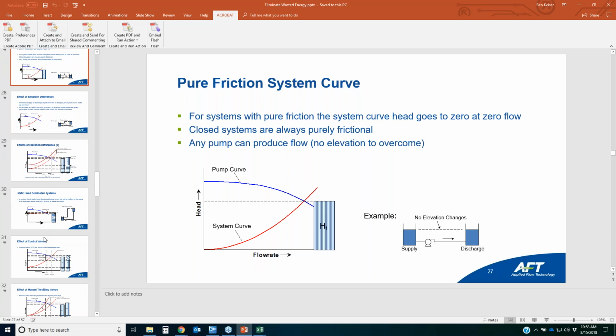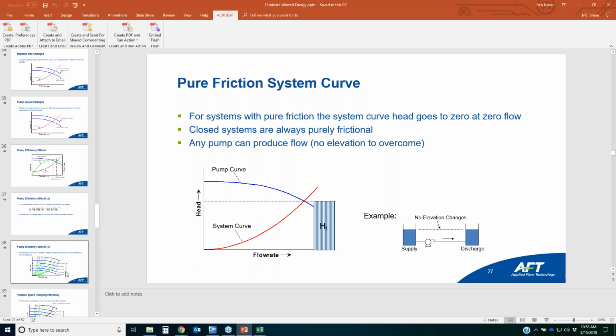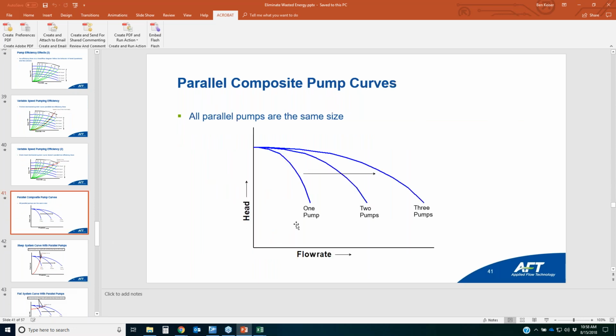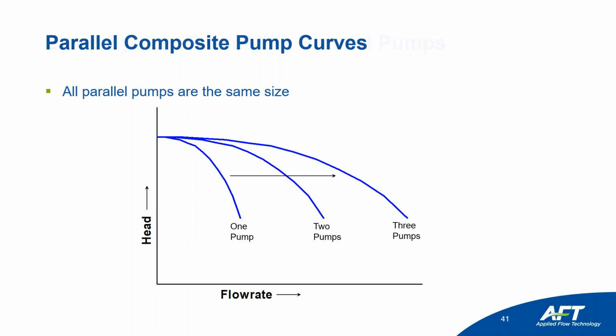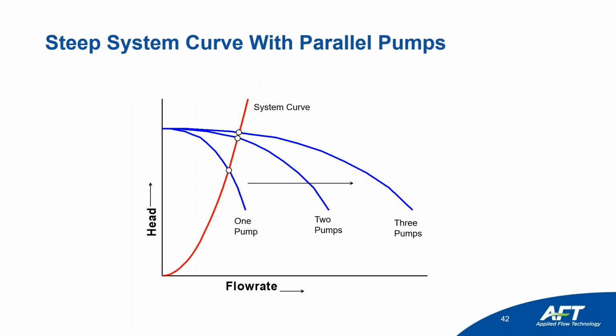And essentially, here's something that is interesting: people will put multiple pumps in parallel to try and get more flow. Okay, so if you remember this from college, this is theoretical where you put more pumps in parallel, you should get higher flow rate. Well, that doesn't happen. Okay, it depends on what your system curve looks like. If you have a steep system curve like this where you have a lot of frictional resistance, you can clearly see how adding more pumps in parallel does not generate that much more flow. So this is an excellent way to show people that just adding more pumps in parallel, that's not going to do it. It's going to make your system run worse. You're going to have more problems, more efficiency issues, and it's not going to operate well.